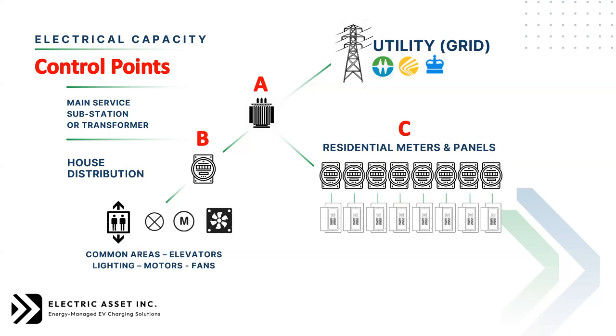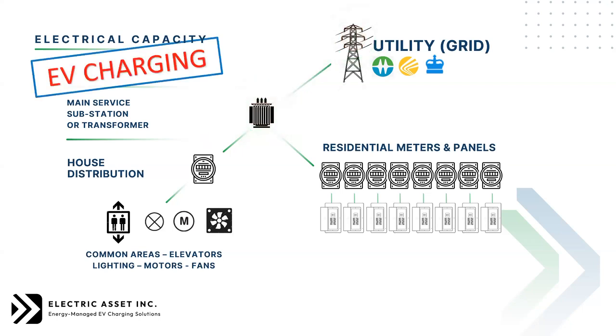So we're looking at all three of these centers as control points or possible areas where capacity has to be taken into account. The idea is to protect your main transformer from overheating or faulting, and to make sure you're not burdening the utility grid through overuse of the transformer. So we get into EV charging - essentially, by routine, we go to the existing house service and try to see if there's available capacity on it.